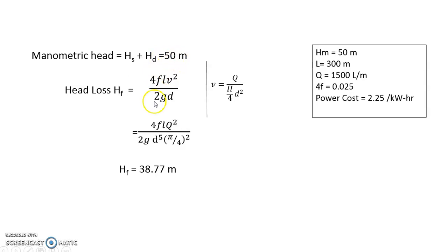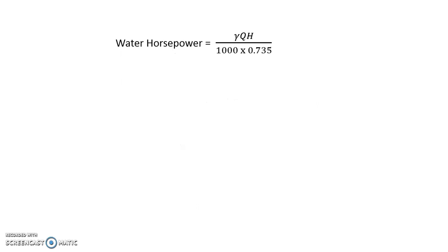Now manometric head is 50 meters, head loss is 38.77 meters, so the total head against which the pump has to work is 50 plus 38.77, altogether it is 88.77 meters.